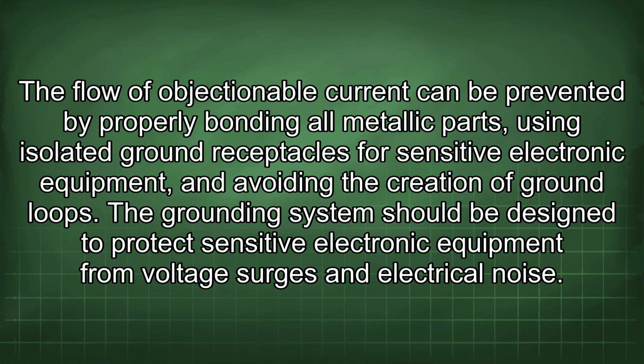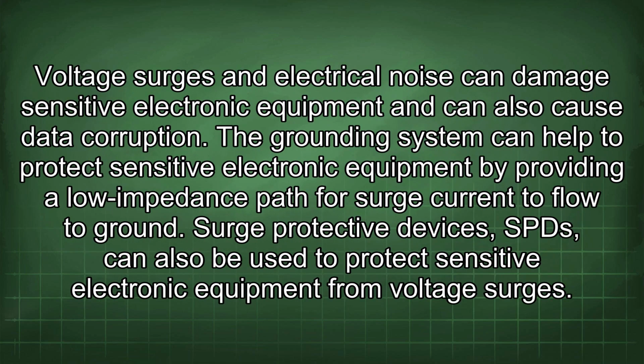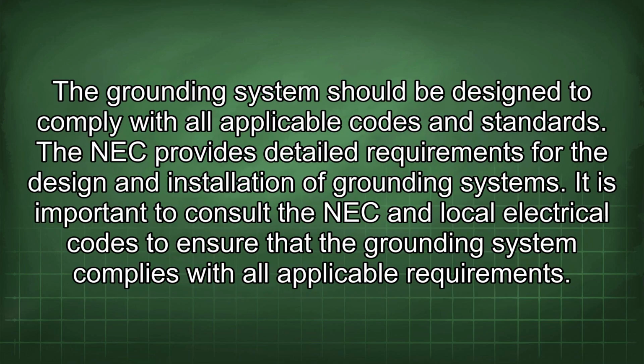The grounding system should be designed to protect sensitive electronic equipment from voltage surges and electrical noise. Voltage surges and electrical noise can damage sensitive electronic equipment and can also cause data corruption. The grounding system can help to protect sensitive electronic equipment by providing a low impedance path for surge current to flow to ground. Surge protective devices, SPDs, can also be used to protect sensitive electronic equipment from voltage surges. The grounding system should be designed to comply with all applicable codes and standards. The NEC provides detailed requirements for the design and installation of grounding systems.